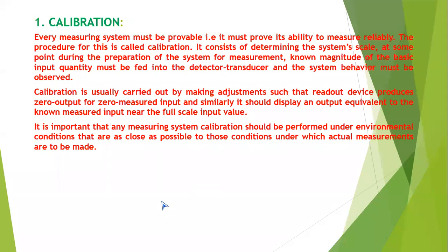So next come to the point, the definition of calibration. The definition of calibration is also very important for mechanical engineers, because we are always using micrometer, vernier caliper, vernier height gauge, vernier depth gauge, and resistance thermometers, thermocouples, thermometers, and any instrument where precision or sensitivity is required in the measurement, you have to calibrate every year or once in 2 years.